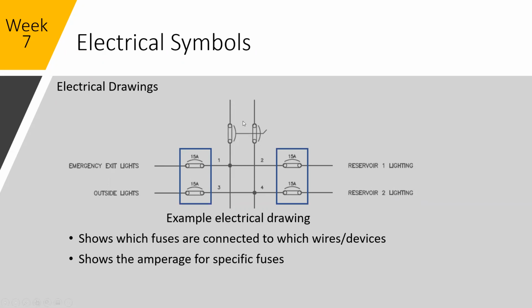At the top here, this is a circuit breaker or a switch being shown that it has a linkage between them. So when this switch is thrown, both of these will open and close at the same time, where these ones, since they're fuses, this is kind of confusing because this could also be construed as a breaker, but these ones are actually fuses. Again, just indicating that this is a single fuse supplying this lighting.